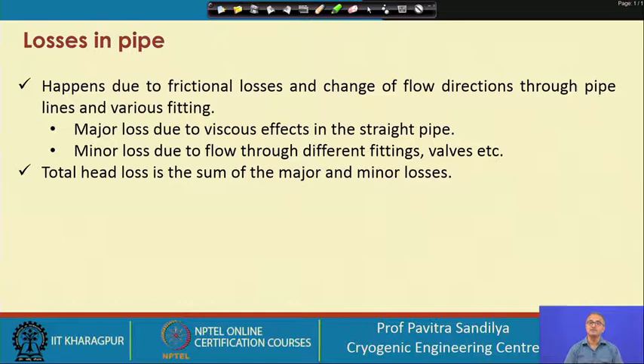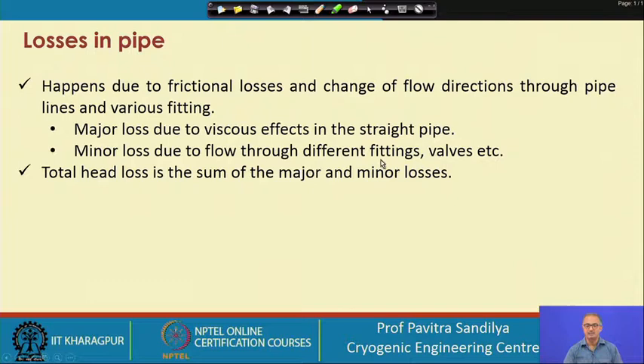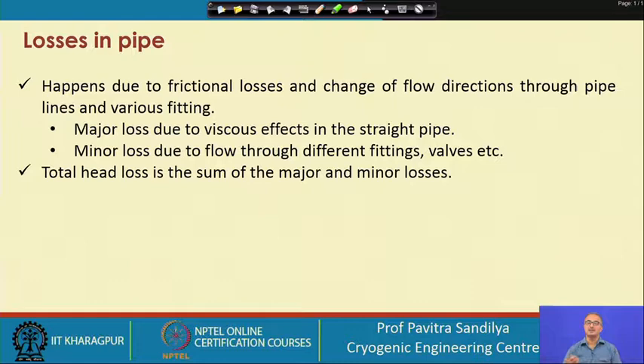These kinds of drags result in the loss of energy of the flowing fluid, which necessitates the use of a compressor or pump during flow over a long distance. In natural gas systems we need compressor stations from distance to distance to reenergize the gas so it can keep flowing. There are major losses in straight pipelines and minor losses through fittings and valves. Major and minor are just nomenclature — major refers to straight pipe losses and minor refers to fittings, valves, entrance effects, exit losses, and changes in cross-sectional area. The total head loss is the summation of major and minor losses.